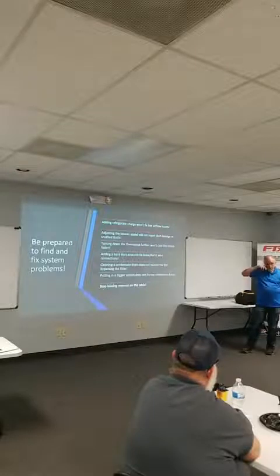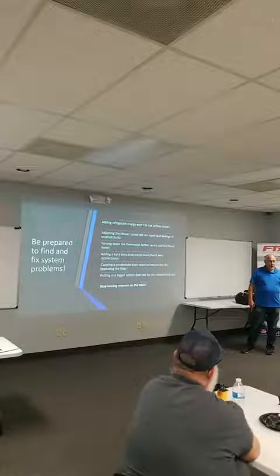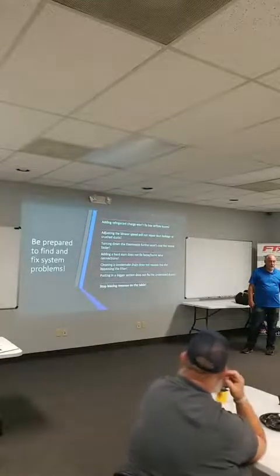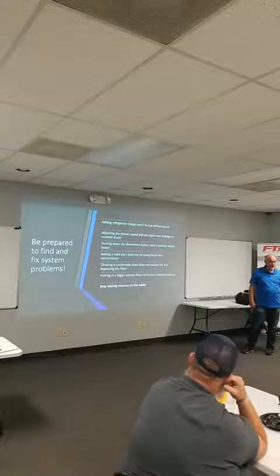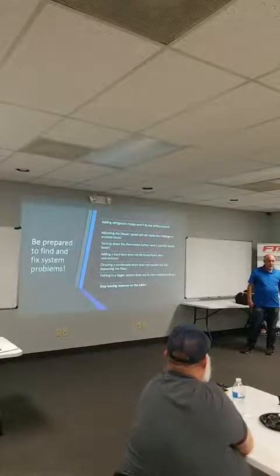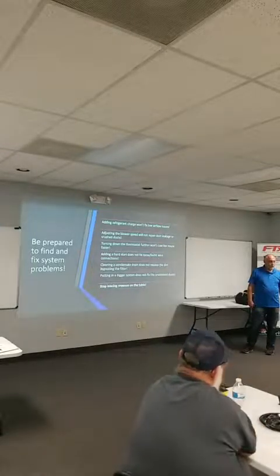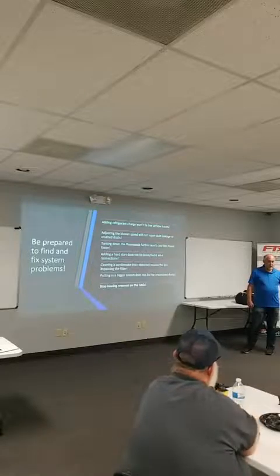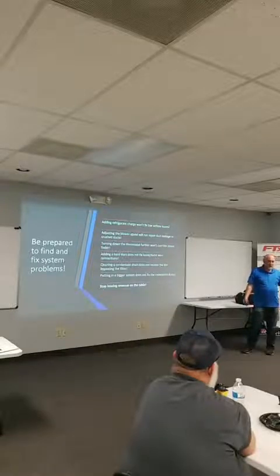Condensate lines, right? It's another big pet peeve of mine. How many times do you think I've cleaned my condensate line in 20 years in my house? Well, twice. 13 years in my house. Twice. Never needed to. Never ever need to. What kind of water is it that goes down a condensate line? Distilled water. So anybody got a CPAP in here? Alright, so when you take your CPAP, you go to Acme and get a bottle of distilled water, you don't ever notice the dirt in the bottom of the distilled water? No, because it's not there, right?